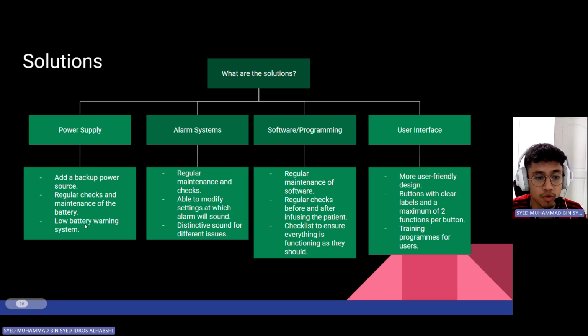There should also be a low battery warning system to warn users when the battery is low so that they can take immediate action before or after infusing the medication into the patient. Secondly, for the alarm systems, regular maintenance and checks should be made. They should constantly check and test the alarm system by covering the tube, for example, to check whether the alarm system is working properly. This is to ensure that in the event an actual problem occurs during the infusion, the alarm will actually sound properly and is very accurate so that the users can take action immediately.